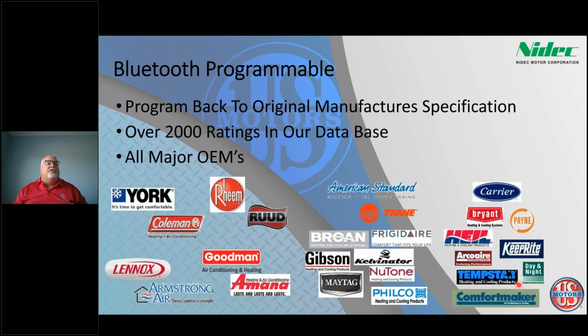We have over 2,000 profiles that we've either gotten from an OEM or literally gone out and purchased the constant torque motor from a wholesaler and brought it into our lab and backwards engineered what torque values we need for that specific model. So on all these motors, there's a lot of times it's called program ID or customer ID. I can show you where to find those here in just a second.